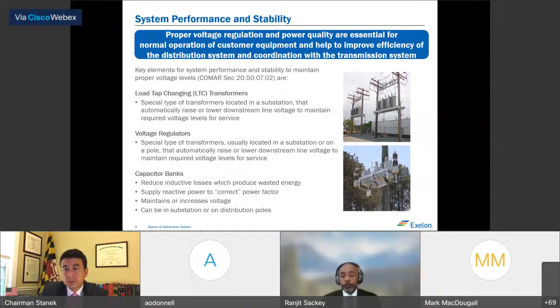So here are some tools that we use for voltage and efficiency. We have load tap changing transformers and voltage regulators. These are special transformers that automatically raise or lower downstream voltage to maintain it within an appropriate range. We also have capacitor banks that are placed at various points in the grid. They also support voltage and the correct efficiency, or what we call power factor, by reducing the power losses caused by inductive loads.